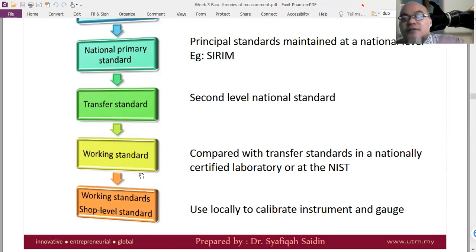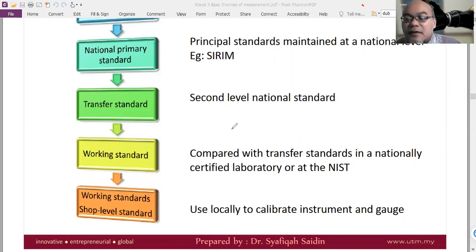And that shop level standard has to be calibrated against the working standard at a nationally certified laboratory, either government owned or private owned. That working standard at the national certified laboratory has to be calibrated against the second level national standard, and then to the national primary standard, and eventually to the international standard. This principle is what we call traceability.